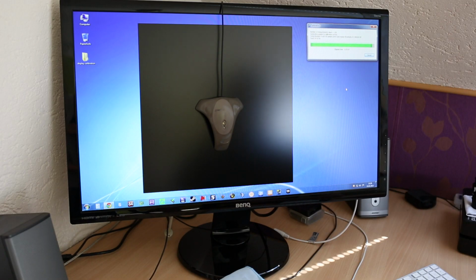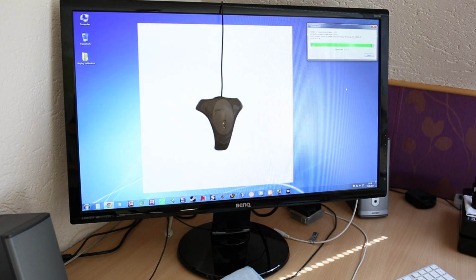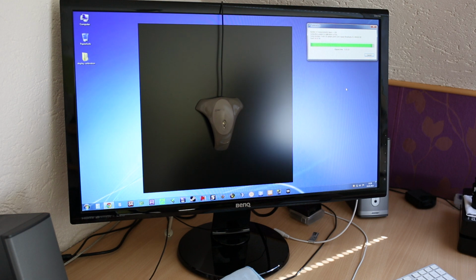Okay, now we're back after it's been a heck of a time. 3 hours and 25 elapsed time so far for this calibration process, and we're at patch 94 of 96, and it's the last 2 patches. It's going to measure, all happening with the white and the black intermittent measurements for the black and white level compensations. Few last things I want to talk about.